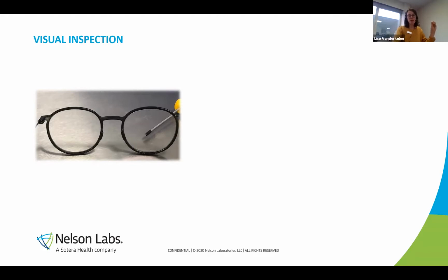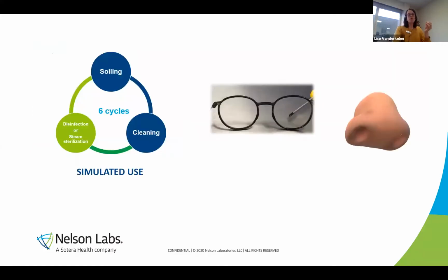This visual inspection is not only done at the last step. No, it is already done during simulated use, because in the simulated use cycle, you're going to use worst case soiling, worst case cleaning, and disinfect or sterilize your device and do this 6 times. And after each cycle, you should visually inspect your device, because if it fails here, you should stop your validation already, even before it actually started.